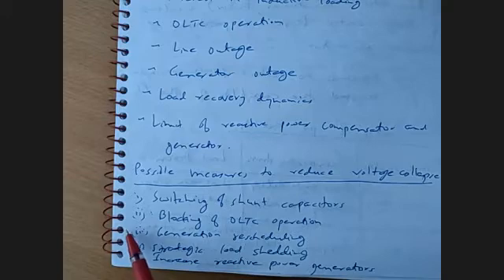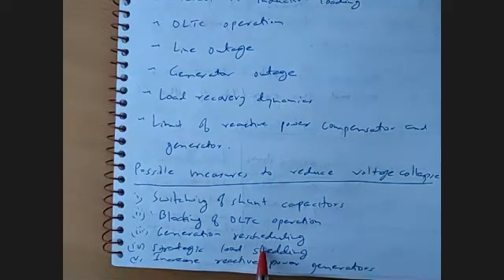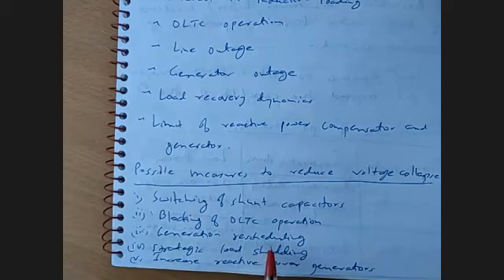Then the second operation, which is generally not feasible, is blocking the OLTC operation. That means we will not do the tap settings operation in the power system. Then we have generator rescheduling. Due to this rescheduling, we decide how much power will be supplied by each generator, and due to this we will be rescheduling the reactive power load on the system. Then we can also do strategic load shedding.